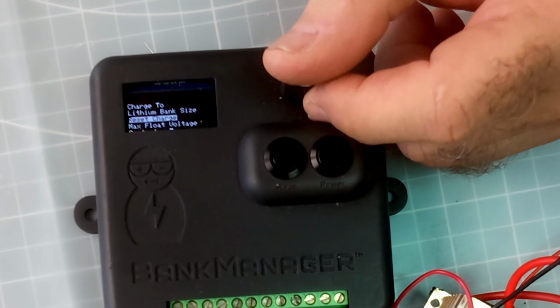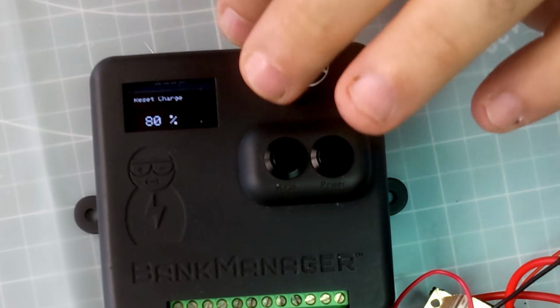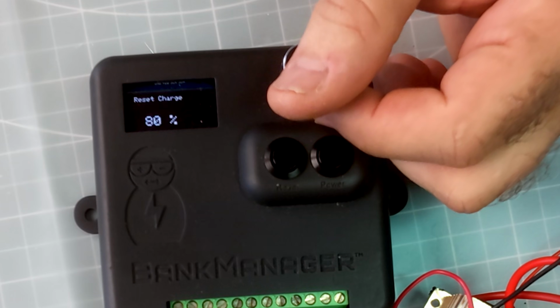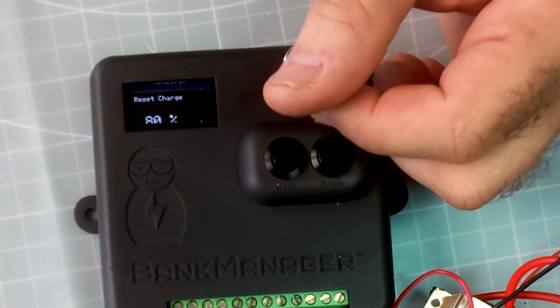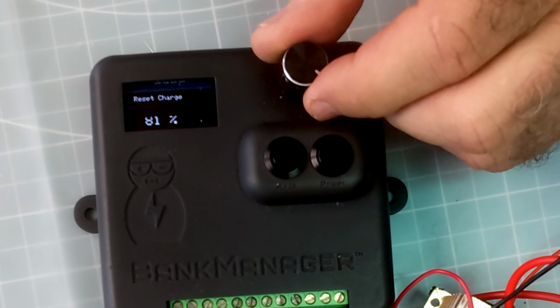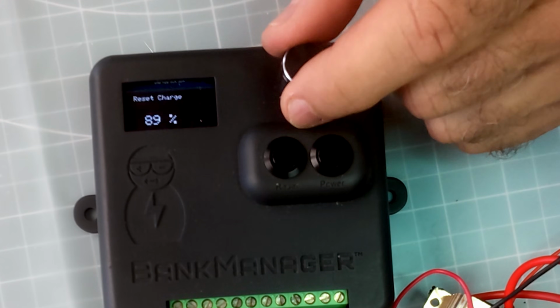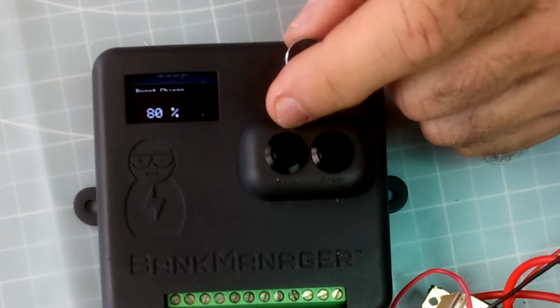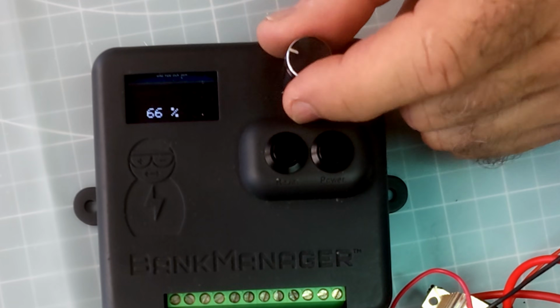The reset charge: by default I set that to 80, meaning until it drops down 20%, you're not a candidate for a full-on recharge cycle, because you don't want every cloud passing to restart the recharge cycle. So we're going to bring that down - oops, I'm going the wrong way - and I think 40 is a good number.